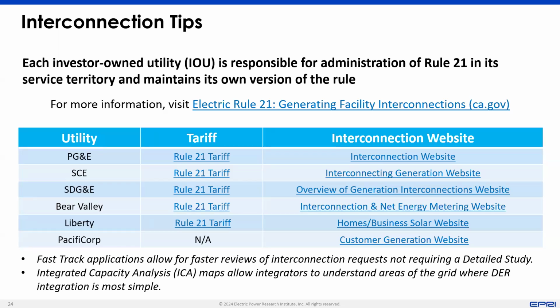There are certain parts of California where installing energy storage, and PV as well, might be easier than others, and you might be able to do different things with it, such as exporting versus not being allowed to export to the grid. That's based on a capacity analysis. Each distribution feeder is different, and might have more PV or more load on it. What they don't want to see happening is all the PV and energy storage discharging at once into the grid and creating backflows of energy. That can have implications that are either dangerous or can lead to outages, so they try to limit that.